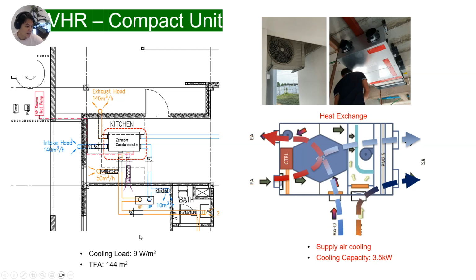You can see here, we made the building cooling load just 9 watts per square meter, and the floor area is 144 square meters. So this compact unit's cooling capacity already fulfills what we need, and is a little bit higher than what we need.